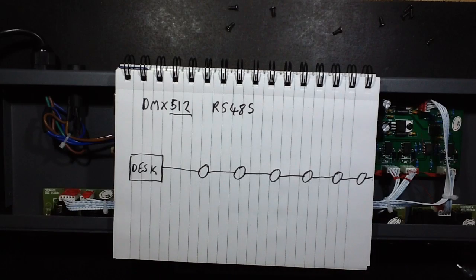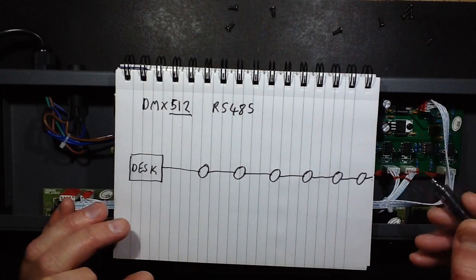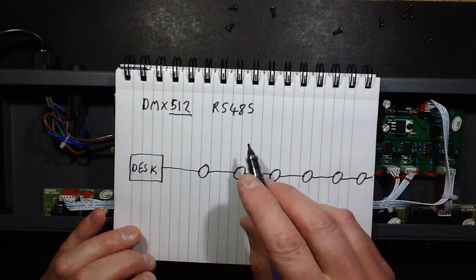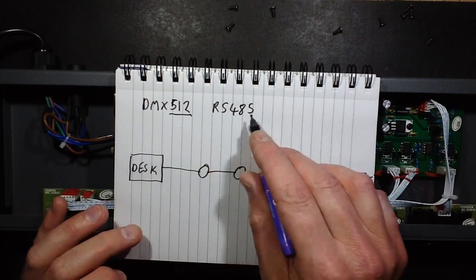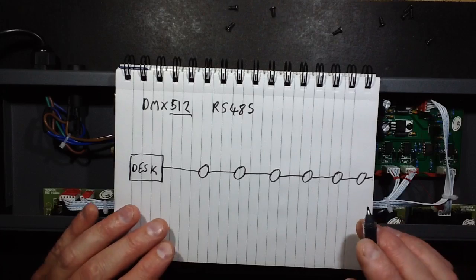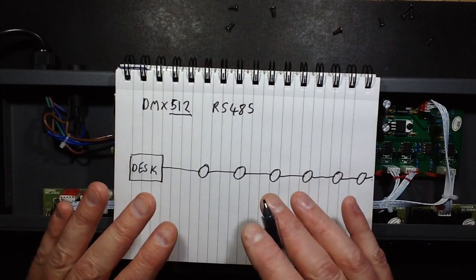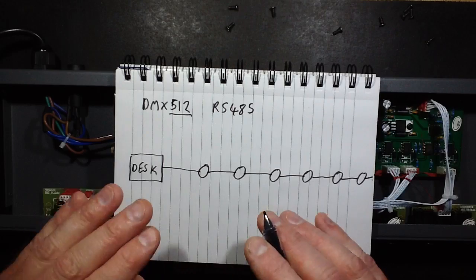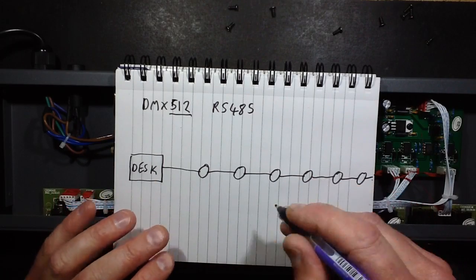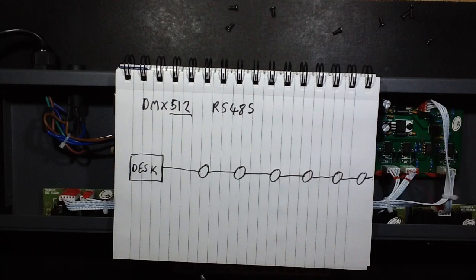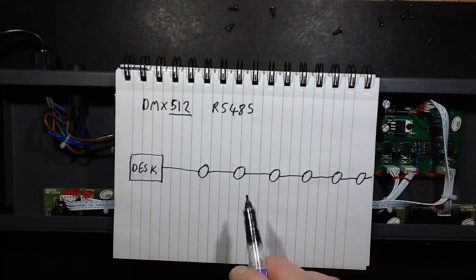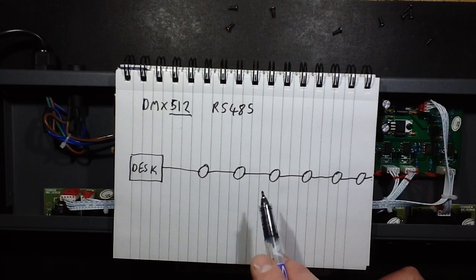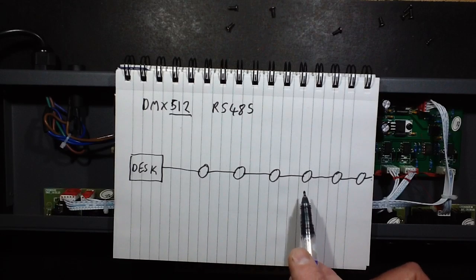However, if you exceed a certain number of lights, in the case of the RS485 protocol the maximum you should have is 32 on a run. Each light represents one unit load. In some cases, some non-compliant lights can actually draw more current than the standard one and that actually reduces the number you can drive.